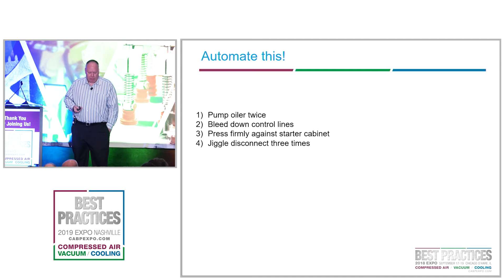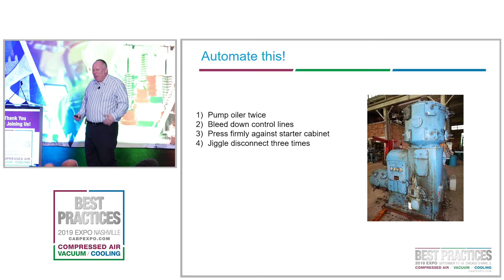This is a true story at a facility with an old reciprocating compressor they wanted to tie into the control system. The question was, what do we do to start this? Because it was older, they said, well, this is what we do: we pump the oiler twice, then bleed down the control air lines, then push against the starter cabinet and jiggle the disconnect, then hit the start button and it comes right up. I said, how do you expect us to automate that?